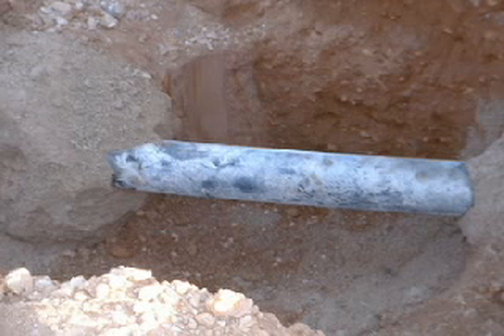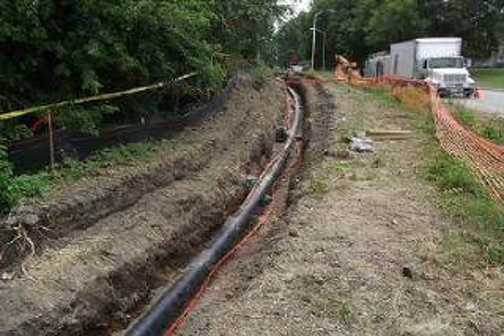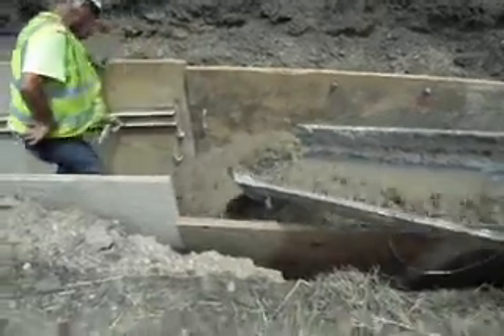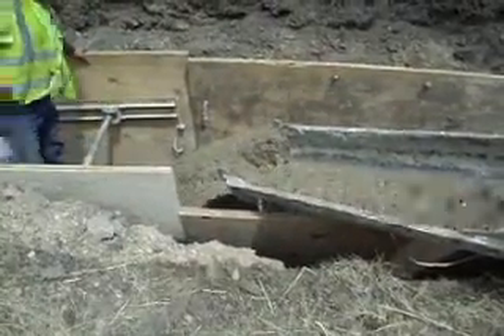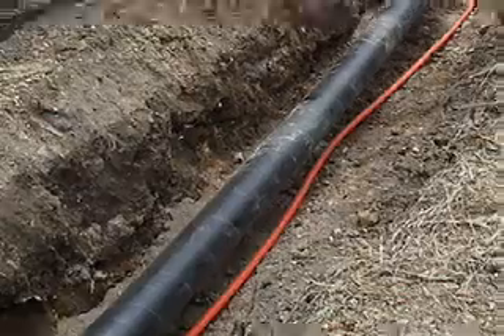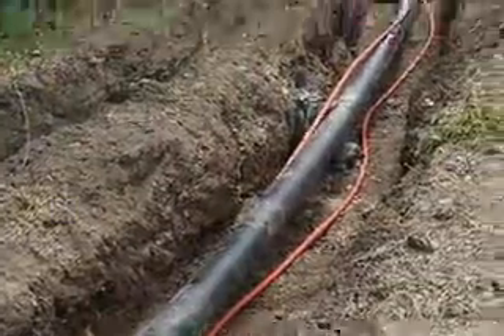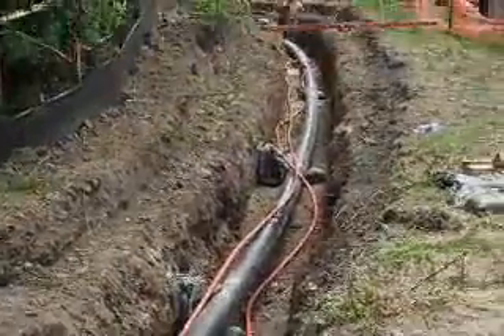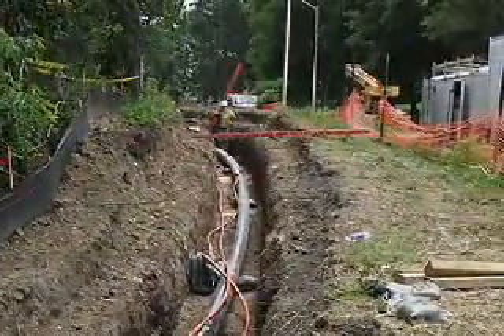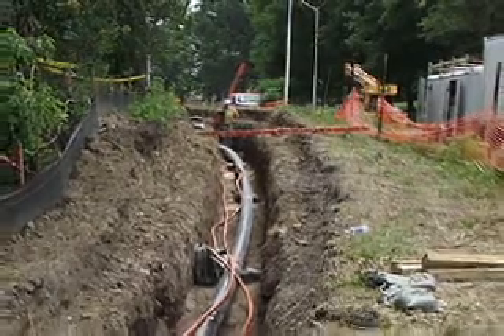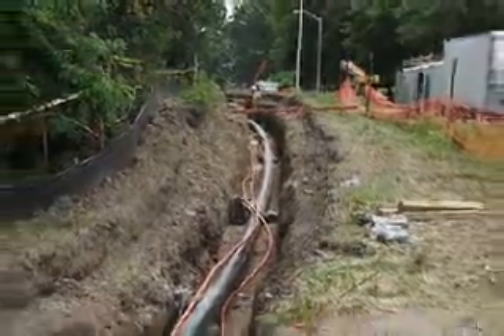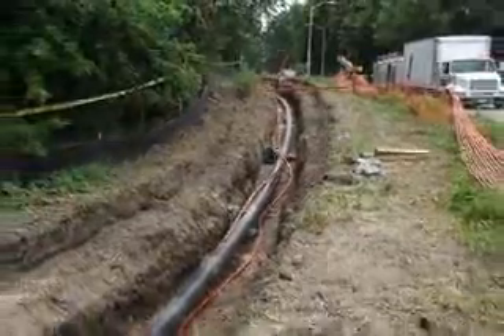Some high-voltage transmission cables are contained within a high-pressure, fluid-filled steel pipe. The coatings on these pipes may be gray, yellow, or black, and may resemble a gas or water pipe. These underground transmission lines are surrounded by either thermal sand or a slurry backfill to allow heat to dissipate, and must be replaced once construction is completed and the transmission line reburied. Other transmission cables are encased within concrete, often called duct packages.